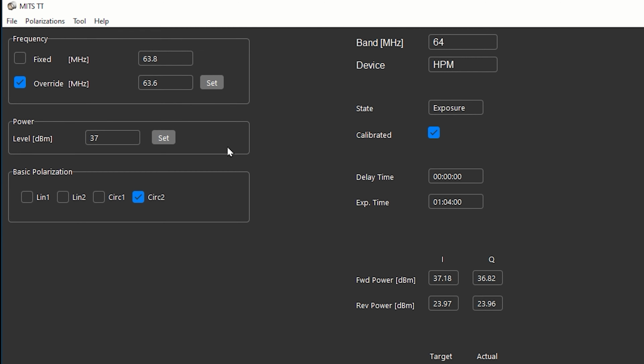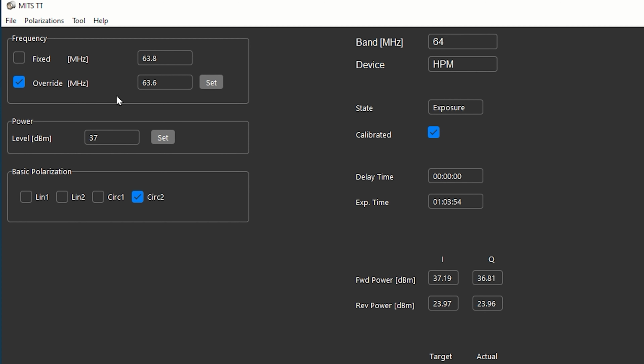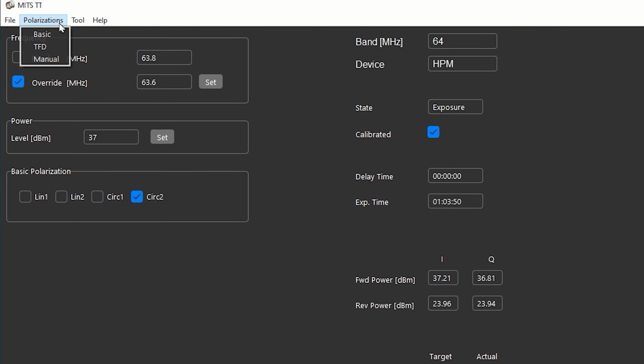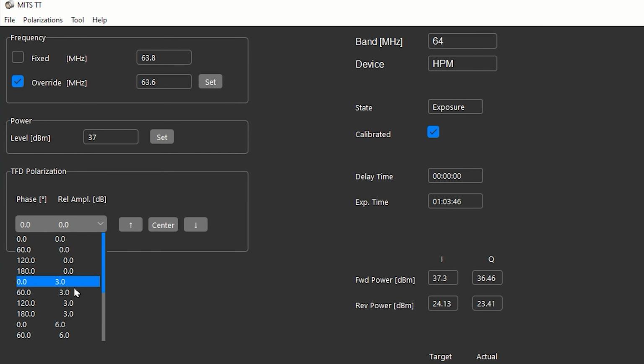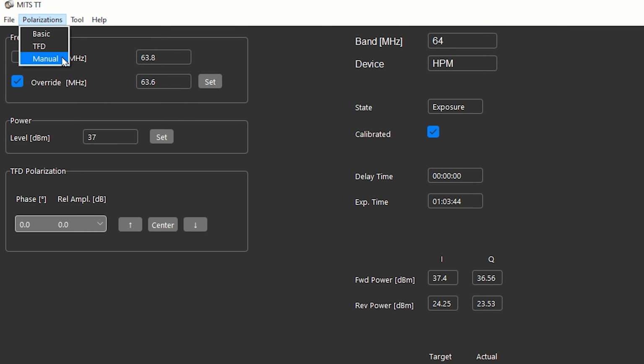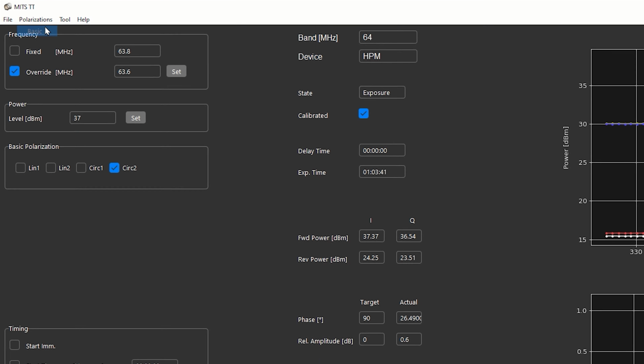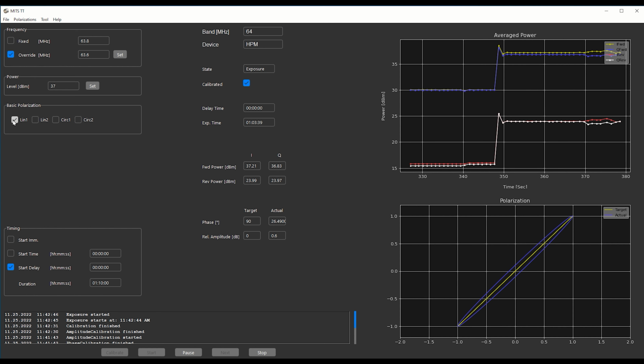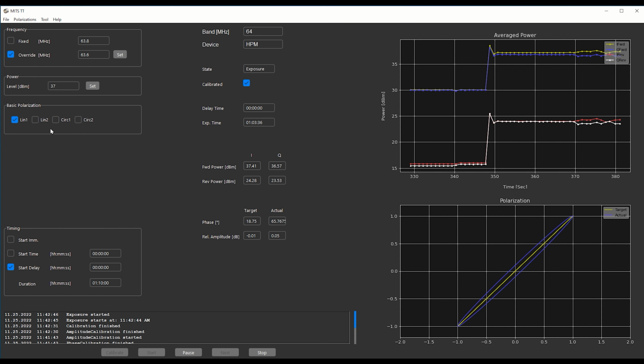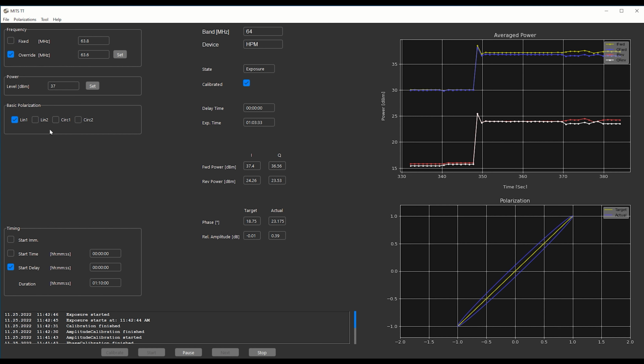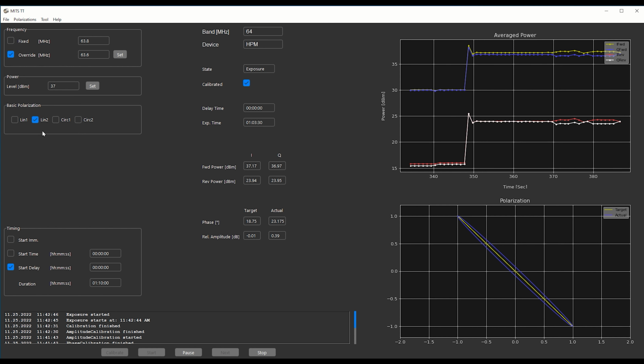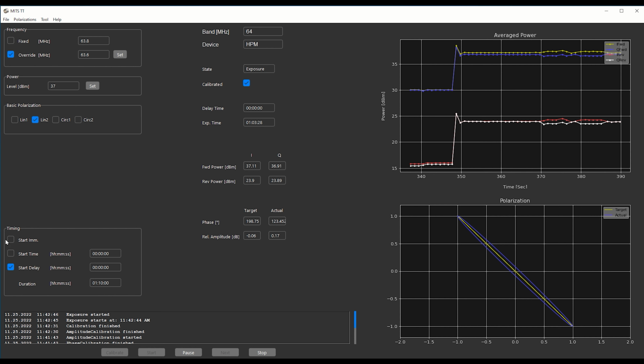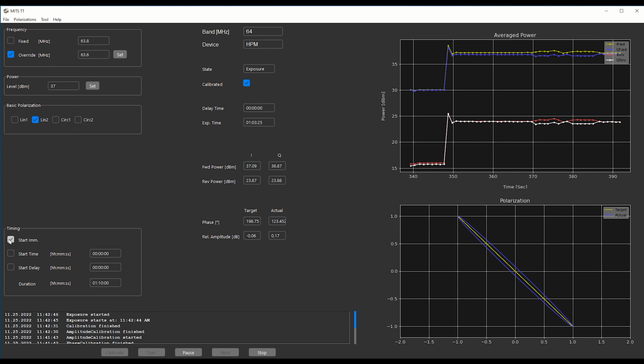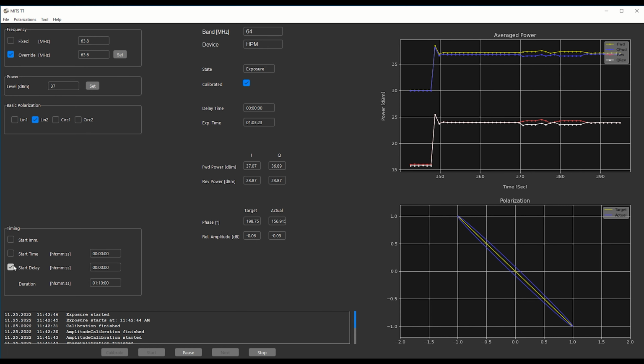Underneath this, we set our exposure polarizations. This can be done if you go back to the top to the menu. There's either the basic polarizations, the pre-programmed TFD polarizations, or completely customizable polarizations. The 4 basic polarizations include 2 linear and 2 circular polarization. And this, depending on what you choose, changes what you see here on the left. Underneath, you can decide if you want to do a timed exposure. So you can set the start time to immediately, you can put a start time that you require or a delay on it, and a duration of your exposure.